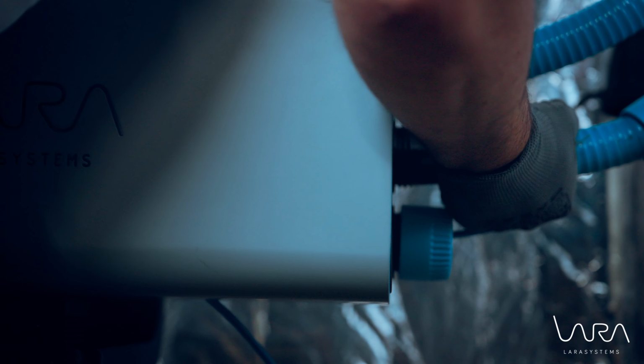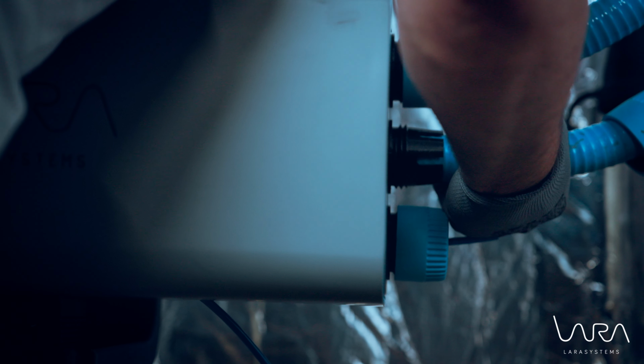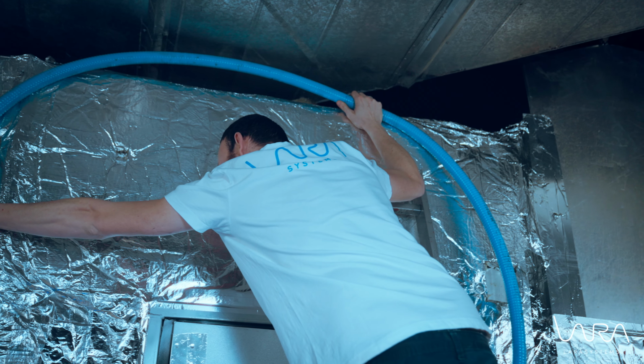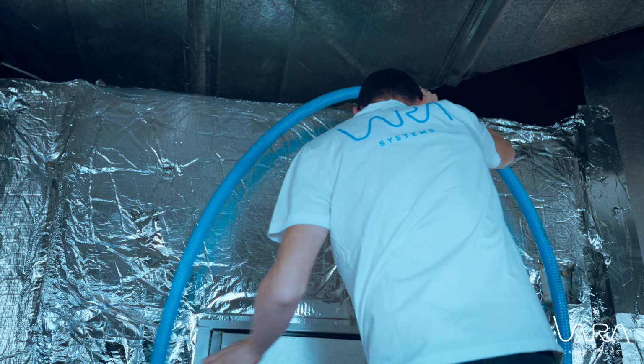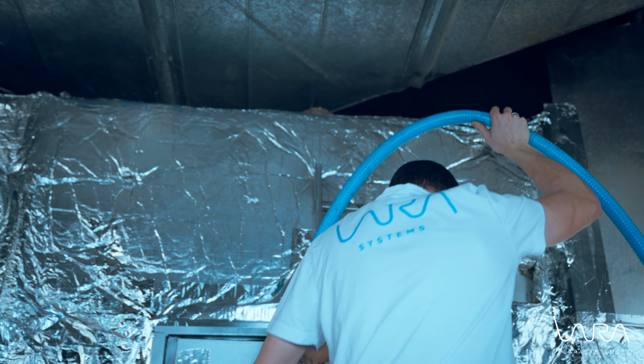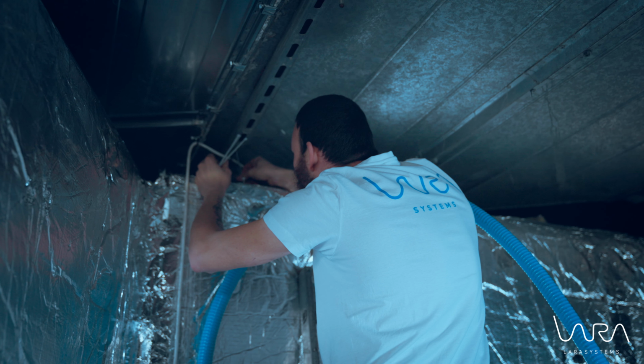Tighten the clamping nut so that the joint is stable, but the pipe is not damaged. A connection that is too loose can cause leaks or connection failures, while over-tightening can damage the pipe or the connector. Repeat the same operation for the connection of every additional pipe.